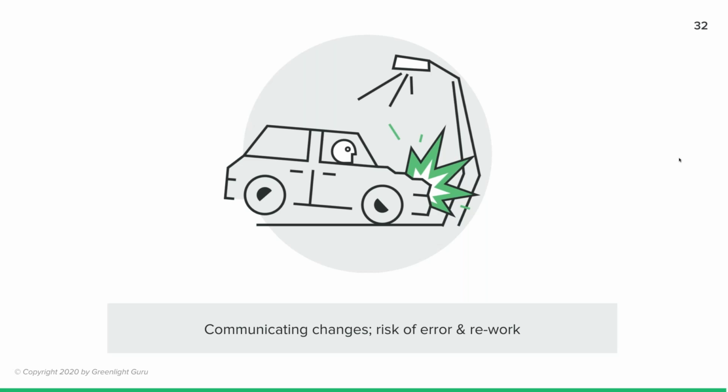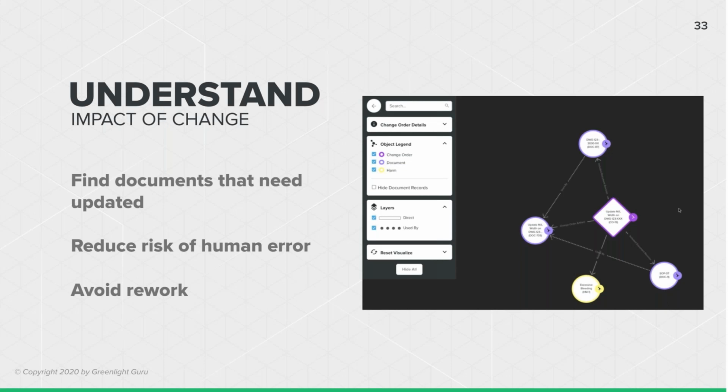But when we traced it back to the design matrix, we found that we did specific testing with this width. We chose this width because it met a user need, and we weren't able to make that change. Whereas if you didn't have clear information, you might have gone and made the change and led to a problem down the road. So with this specific example, we want to make sure that we find the documents we need to update.